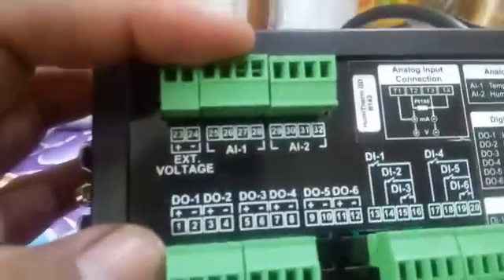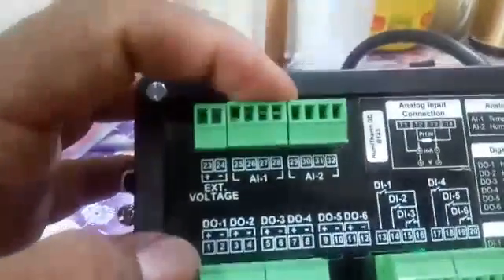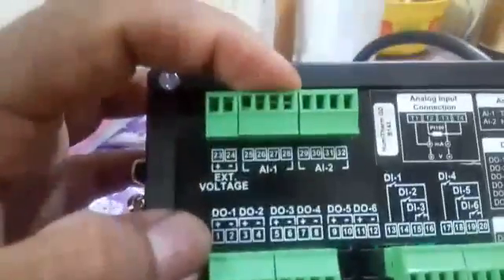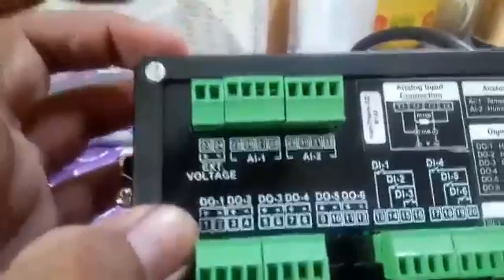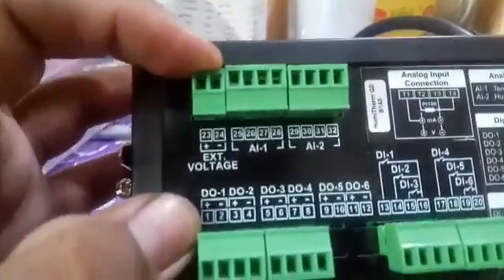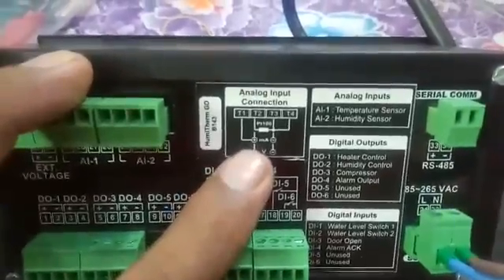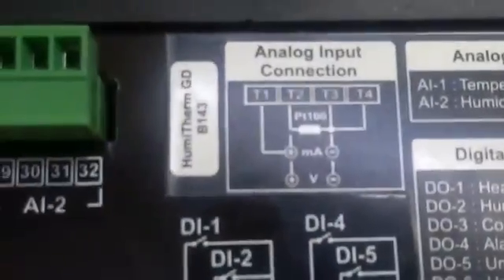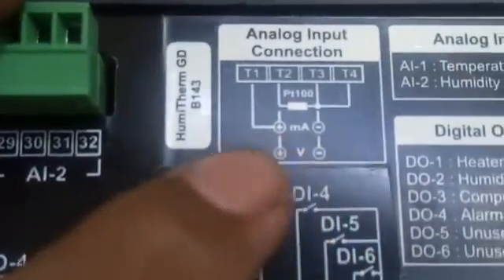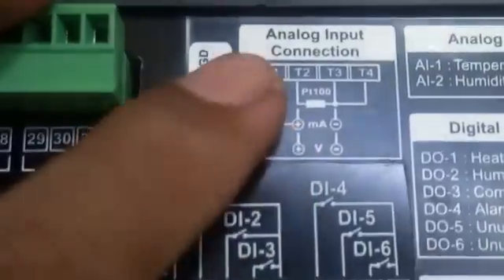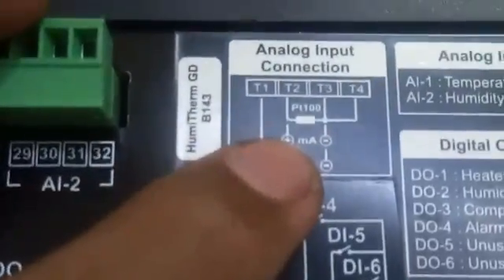Here you can see: this is input one — you have to give 4-20 milliampere here. The second input is humidity and temperature. You can connect humidity here and temperature here, or you can change them — no problem. This is the excitation voltage — if you want 24 volt, it will come from here. You can see the readings: here you have to connect plus and minus — milliampere plus and milliampere minus.